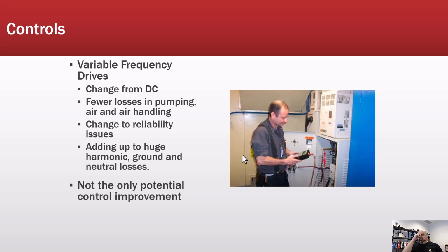So where we're supposed to do things like IEEE 519 and the point of common connection with the utility to protect the utility, we end up with a whole list of other issues such as harmonics, ground harmonics and voltages and currents, and neutral currents, depending on the type of nonlinear loads we're adding to the system.